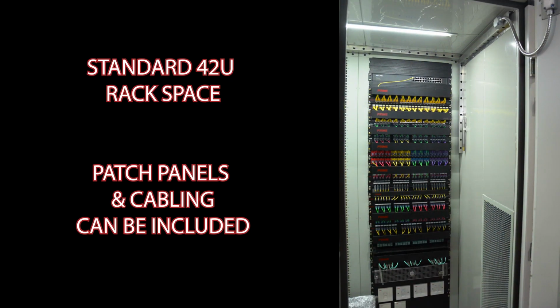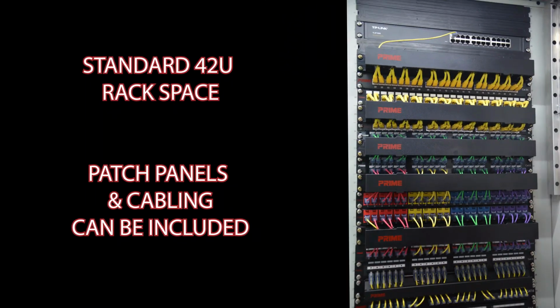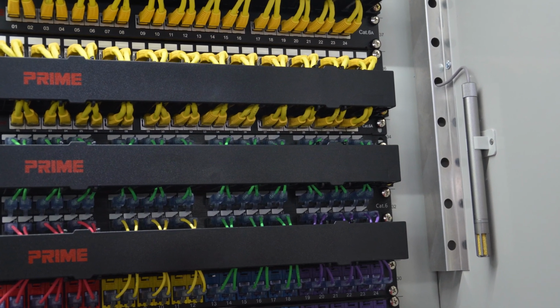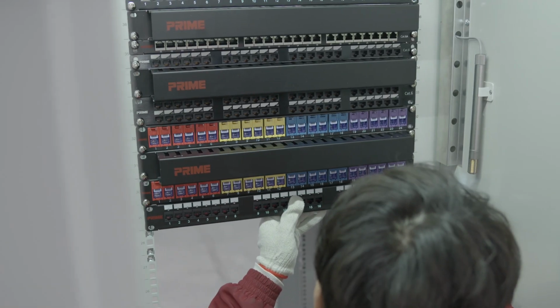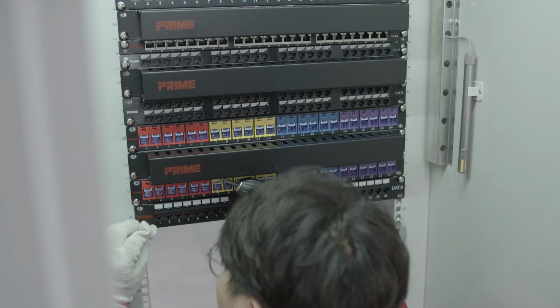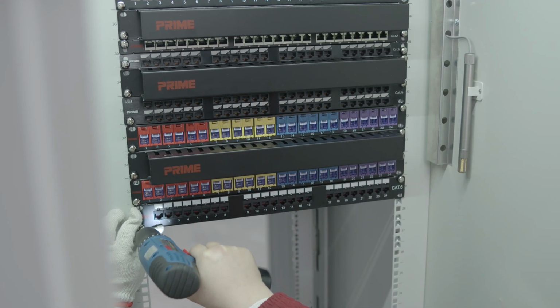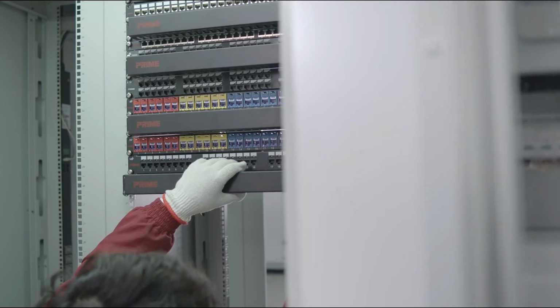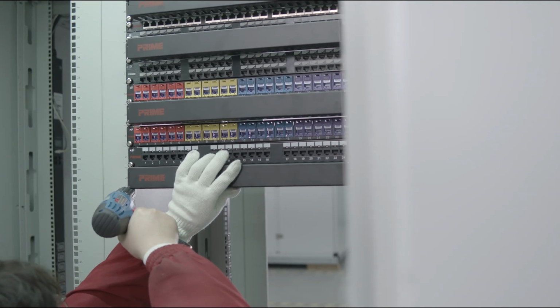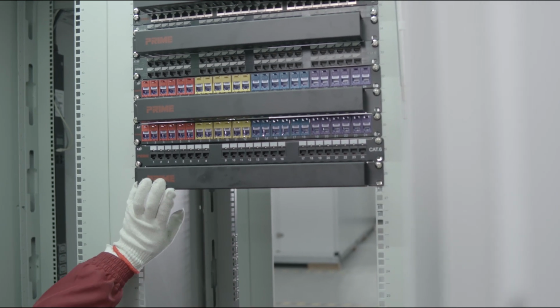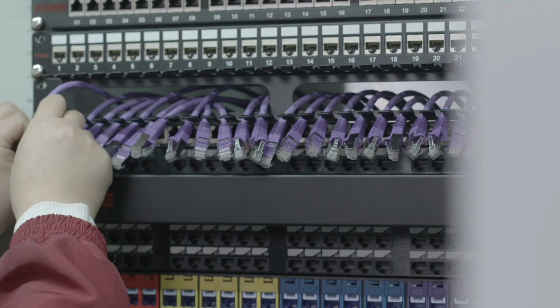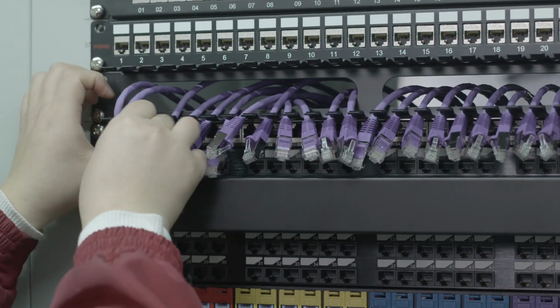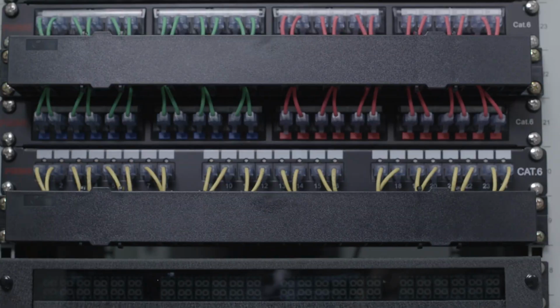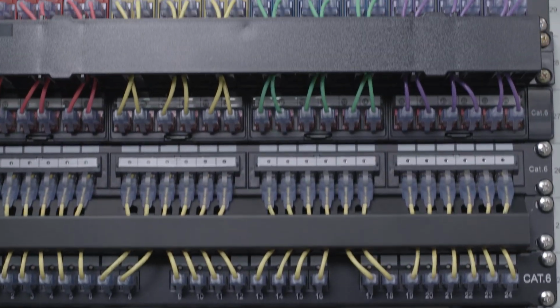Let's continue into the cold aisle where the IT is accessed. There is a thermostat and sensors that measure the temperature and relative humidity at all times. They can be monitored remotely or on the PLC panel. Another reason we call our solution plug and play, one of the major time and cost saving options Prime offers, is that we can install and pre-wire the racks in the MDC to your specifications. Complete with Prime's premium quality patch cables, patch panels, keystone jacks, and faceplates, as well as bulk cable and cable management, all installed at the factory, saving time at the site.